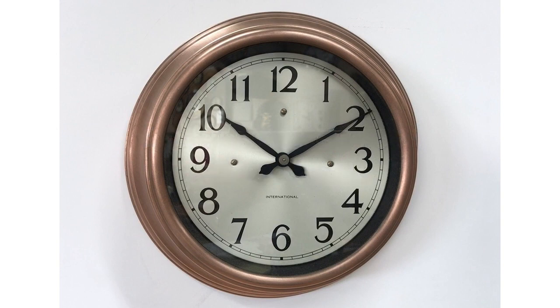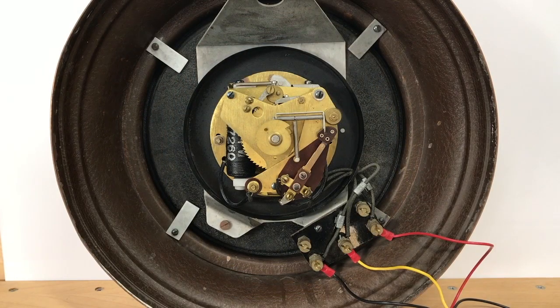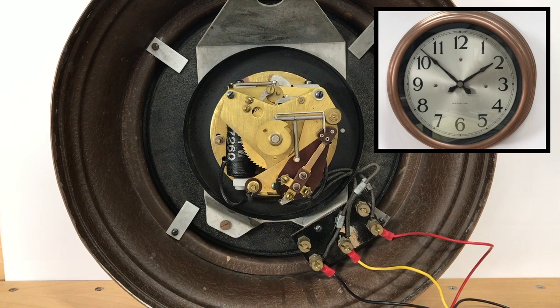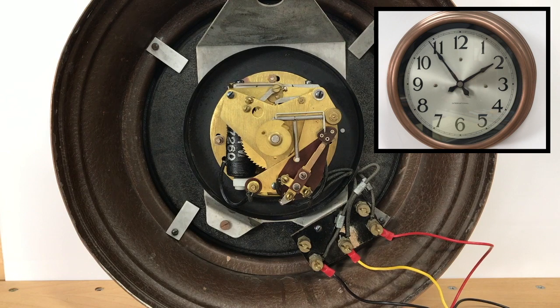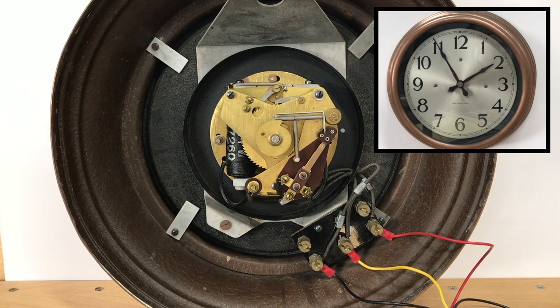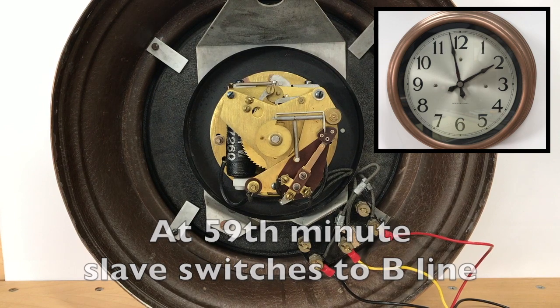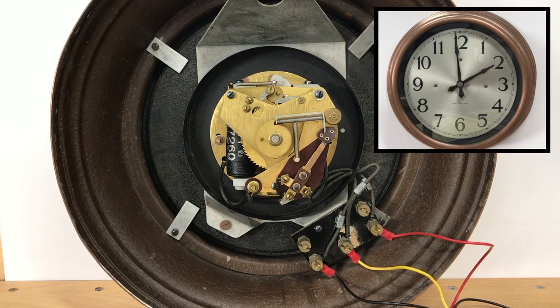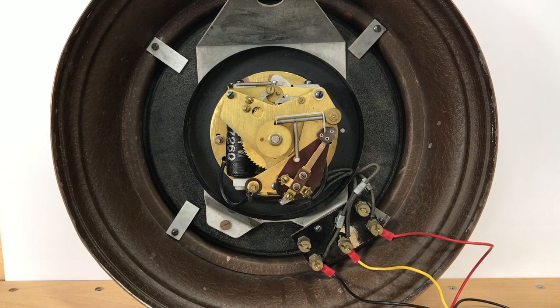I would like you to watch as the correction is made for a clock that is 8 minutes slow. The slave is receiving an impulse on the A line every 2 seconds. As the slave begins to catch up and finally reaches the 59th minute, the A-B switch will switch to the B line and no more impulses will be accepted until the master clock sends a signal on the 60th minute on the B line.